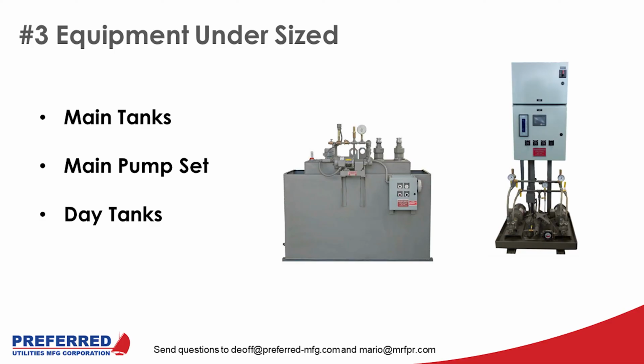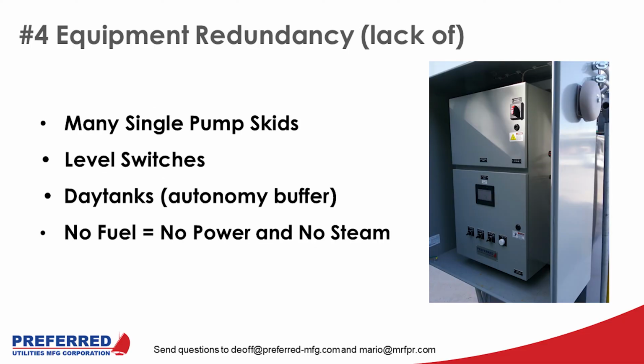Number four on the list of lessons learned is equipment redundancy, or lack of. Equipment redundancy was lacking. Many users were using single pump systems. Many pumps failed due to maintenance, age, or other reasons. Sourcing was not easy in those first couple of weeks because the ports were pretty much controlled by FEMA. So sourcing fuel pumps was no easy task. Some level switches also failed for both high and low levels, and many had no spare parts on hand. So lack of redundancy in those cases could really affect the control of your system.